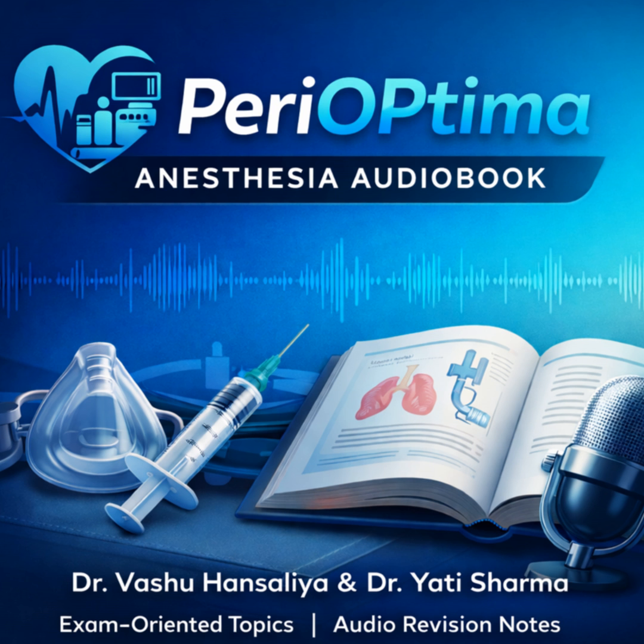Oxygen is forced through a very narrow jet. This high velocity creates a zone of low pressure, like an airplane wing. Exactly like that. This pressure drop actively sucks in, or entrains, a very specific amount of room air through carefully sized side ports. The mask comes with different colored adapters, and each one has a different sized jet and different sized ports.